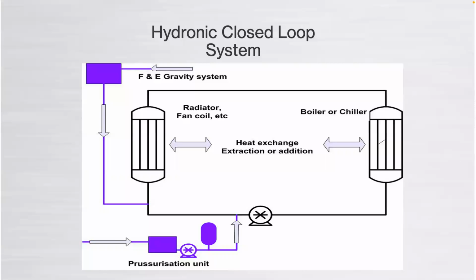Typically most systems are now pressurized with a pressure vessel and some form of pressurization unit or an RPZ valve. So you'll have maybe a glycol fill unit that tops up your system, depending on where you are in the US or Canada, or you'll be straight off the mains water RPZ. But if you've got an RPZ makeup system and you do have water leaks, how do you know about it unless you've got some form of an alarm?